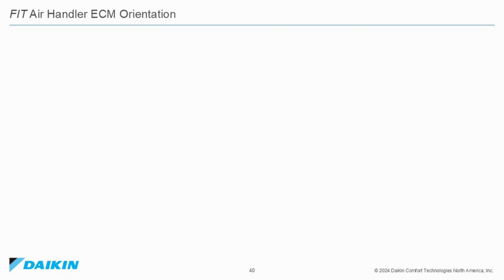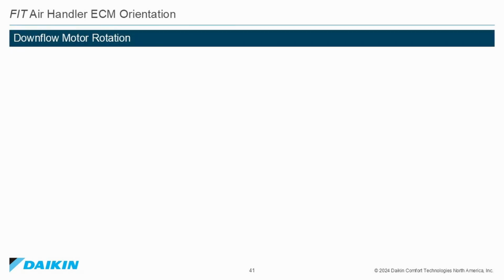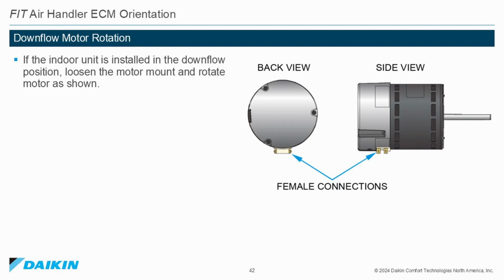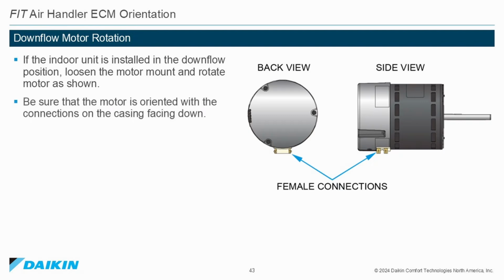FIT Airhandler ECM motor orientation. Downflow motor rotation. If the indoor unit is installed in a downflow position, loosen the motor mount and rotate the motor as shown. Be sure that the motor is oriented with the connectors on the casing facing down.